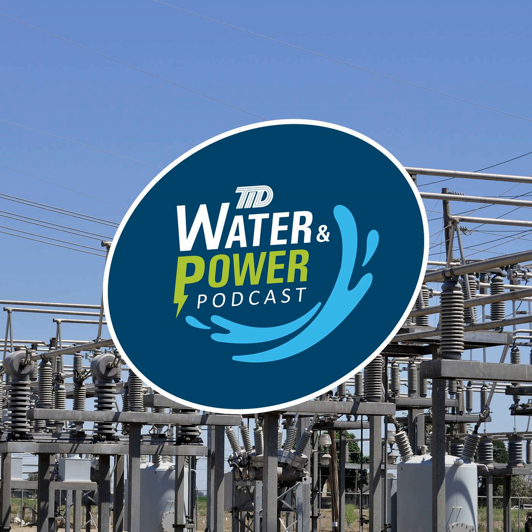So when distributing to our community, we don't physically have the space to do that at that voltage level. And the larger the step the transformer takes, the bigger those transformers have to be. We don't have space in our community, nor does it make sense economically to distribute that way. So we actually distribute at a lower voltage, meaning smaller spacing and smaller equipment.